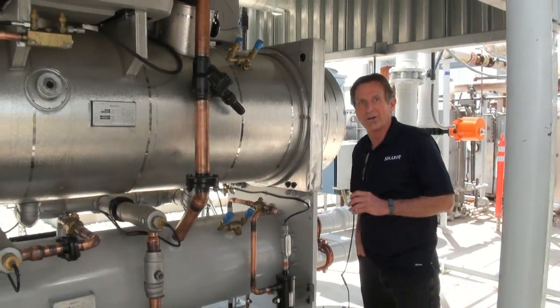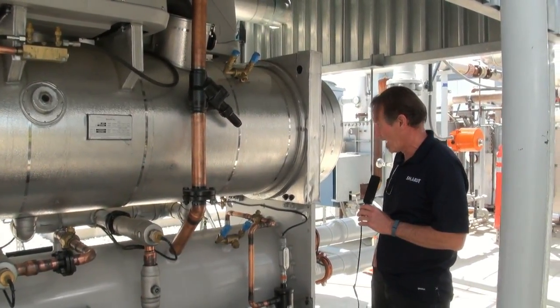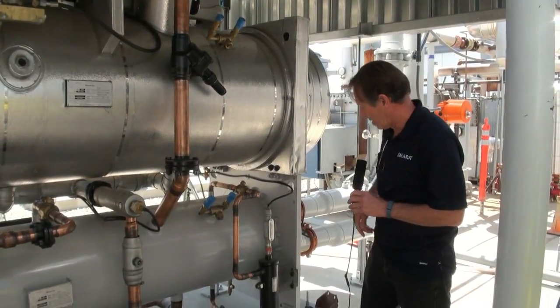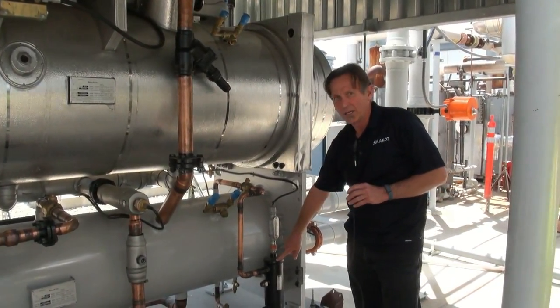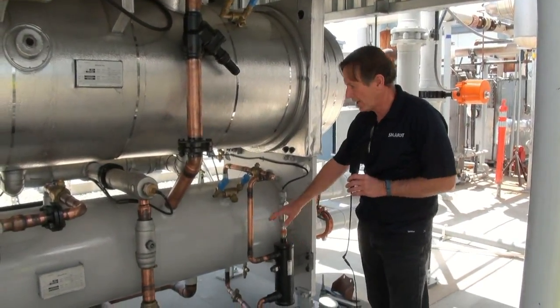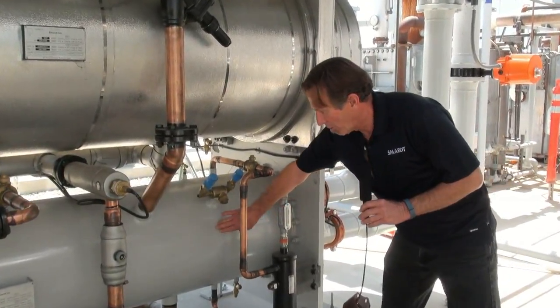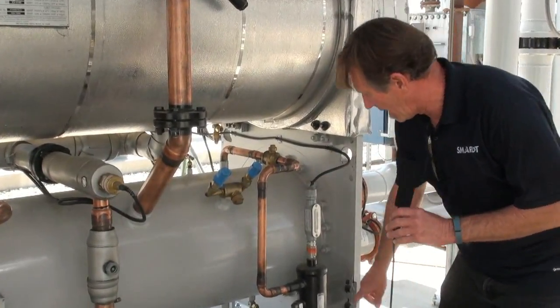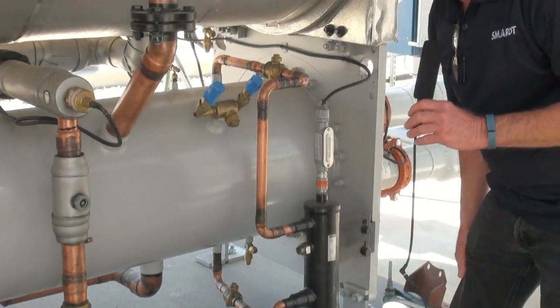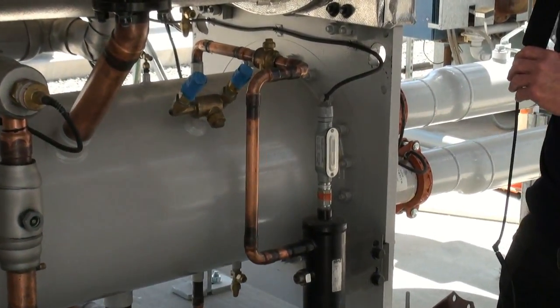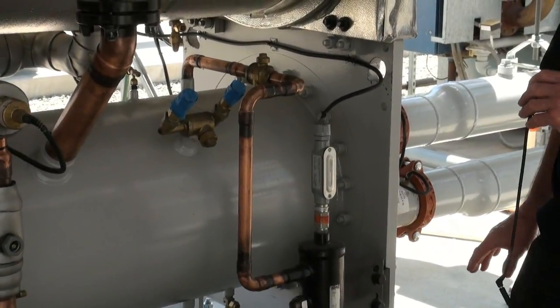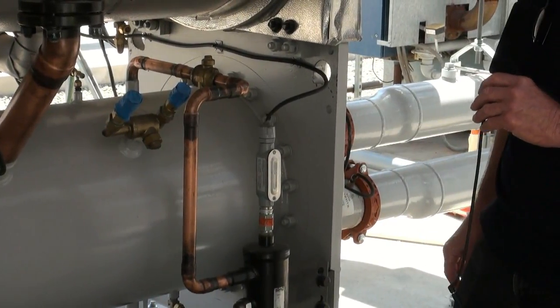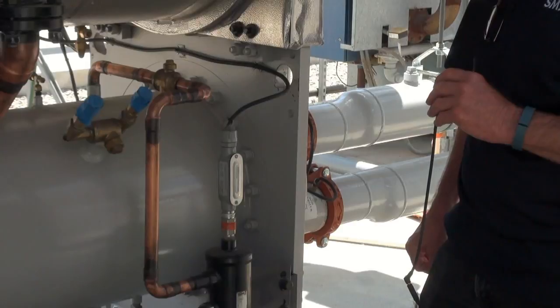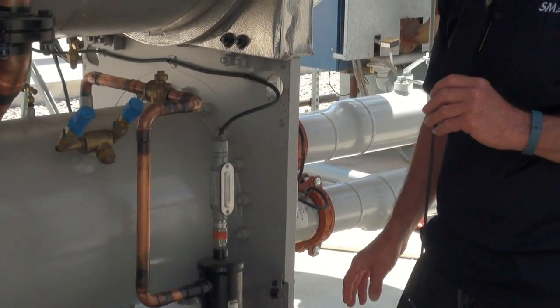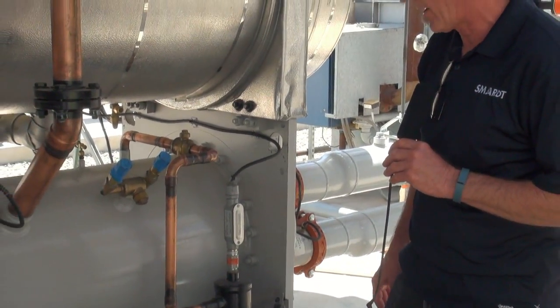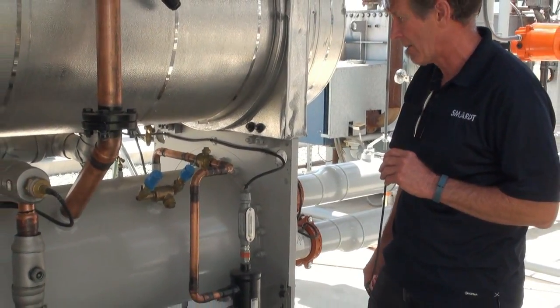All right, we rolling? All right. What we have first off is a level sensor. This senses the level in the condenser barrel. There is a sight glass there. You may or may not see a level in the glass. It just depends on where the level is set. 1 or 2% can put you above or below that sight glass, so you may not see any level in it.